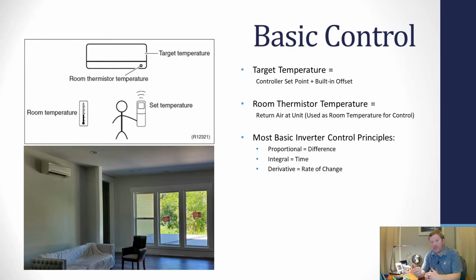So we start out 8.5 degrees apart. The system sees that. It's going to ramp up. It's going to run harder because it needs to recover 8.5 degrees between the target temperature and the room temperature. Now it's going to monitor how fast it gets closer and closer to that target temperature. And as it gets closer and closer, that derivative factor tells it to slow down. The closer it gets to that target temperature, the more the compressor slows down.